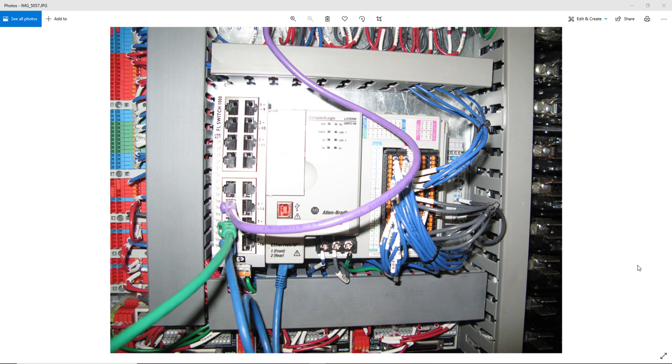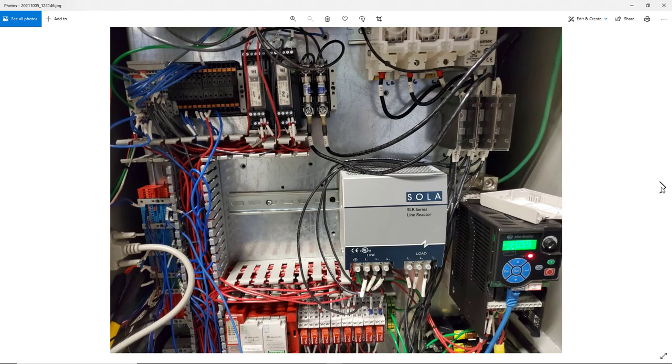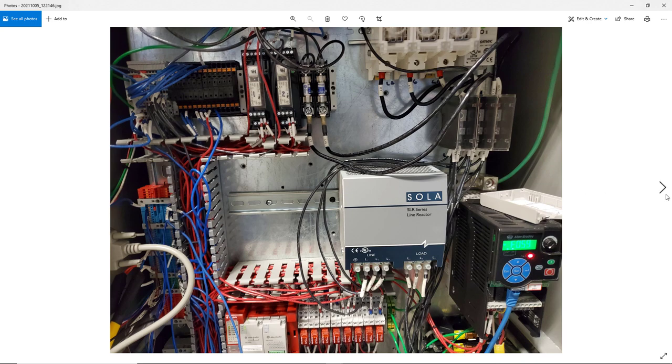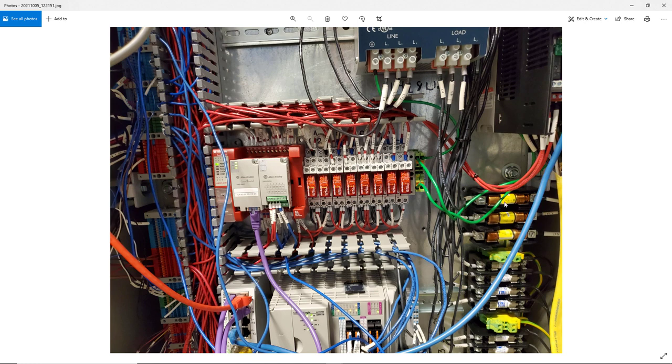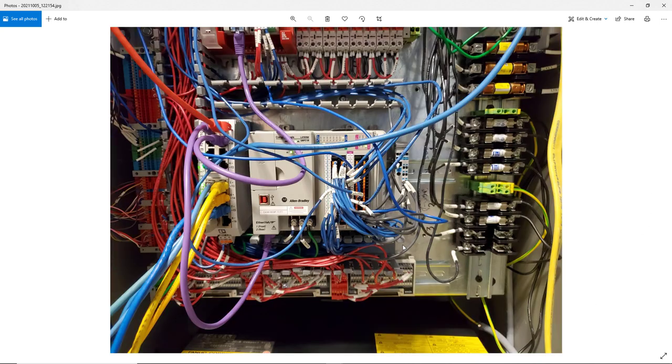So that kind of catches you up with the panel. Now regarding what you don't see is the congestion on the peripheral of the unit. Now this is not exactly the way it is now because that wire duct over to the right over here it's no longer there it's moved over more to the right and we've replaced these fuse blocks with a different size. This is the new line reactor twice the money of the other one but much more dependable and effective. And here you can see that we've increased the space right here between the safety circuit and the PLC circuit and our fuse blocks. And notice that we have smaller fuse blocks now. This fuse block is for the VFD right above it here and these are all for other devices. You can see a little bit of the congestion over here on the left where we have field connections coming into these terminal blocks.